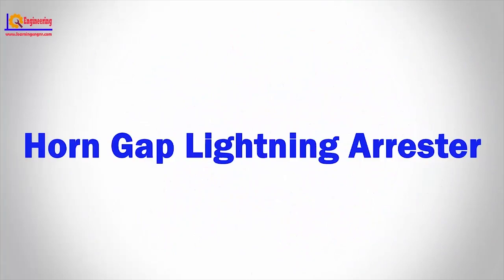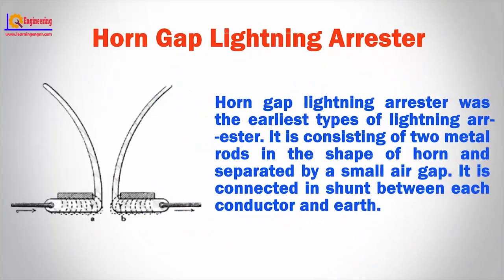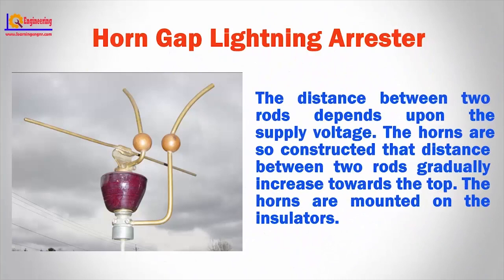Horn gap lightning arrester was the earliest type of lightning arrester. It consists of two metal rods in the shape of a horn, separated by a small air gap. It is connected in shunt between each conductor and earth. The distance between two rods depends upon the supply voltage. The horns are so constructed that the distance between the two rods gradually increases towards the top. The horns are mounted on the insulator.